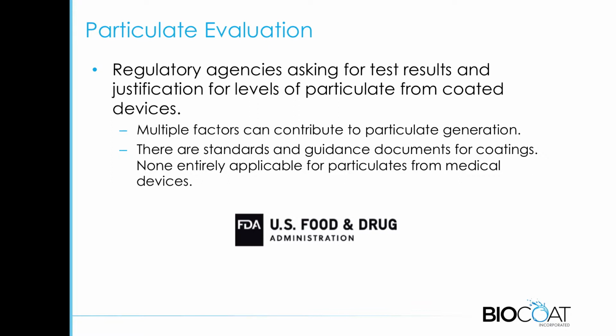Here's the problem: there are multiple factors that can contribute to particulate generation. There are the coatings, but then there's also the device design, how stiff that is. And then the ancillary devices: the sheaths, the guide wires, even the wipes that are on the table. All of those can generate particulates, and so you have to separate that out to really look at the device itself.